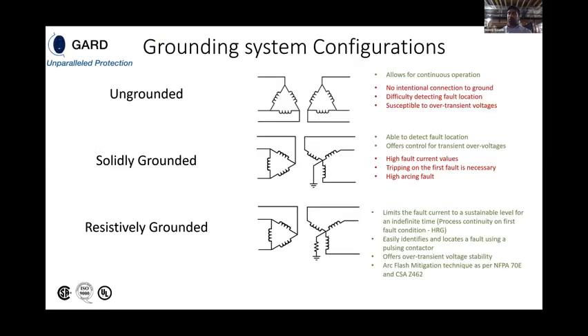Now, in the North American market, we typically see three different types of system grounding arrangements often utilized. Ungrounded systems are utilized about maybe 12 to 14% of the time. It allows for continuous operation in the event of the first fault condition. The only issue is that when a first fault occurs, there may be transient overvoltage conditions which could arise from the unfaulted phases, which could exceed up to 6 to 8 times the line to neutral voltage of the system. This could cause further degradation in the cable insulation and eventually lead to a phase-to-phase failure if it's left in the system for too long.